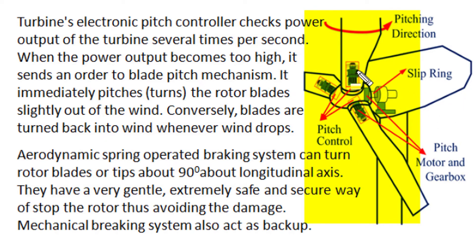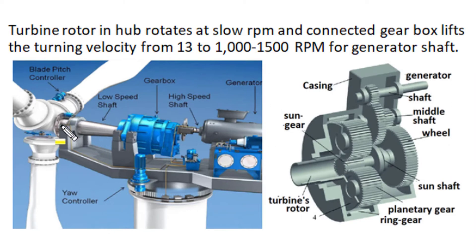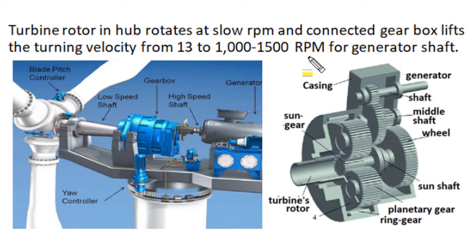In all wind turbine systems, a mechanical braking system is also provided as a backup safety provision. In the turbine, the rotor blade and hub rotate at a slow RPM of 10 to 15 revolutions per minute. The connected gearbox lifts the turning velocity of this high-torque, low-speed shaft to moderate torque and high speed — 1000 to 1500 RPM — as required for the generator in four-pole or six-pole configuration.